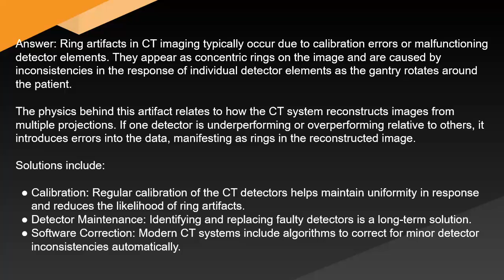The physics behind this artifact relates to how the CT system reconstructs images from multiple projections. If one detector is underperforming or overperforming relative to others, it introduces errors into the data, manifesting as rings in the reconstructed image. Solutions include calibration. Regular calibration of the CT detectors helps maintain uniformity in response and reduces the likelihood of ring artifacts. Detector maintenance. Identifying and replacing faulty detectors is a long-term solution. Software correction. Modern CT systems include algorithms to correct for minor detector inconsistencies automatically.